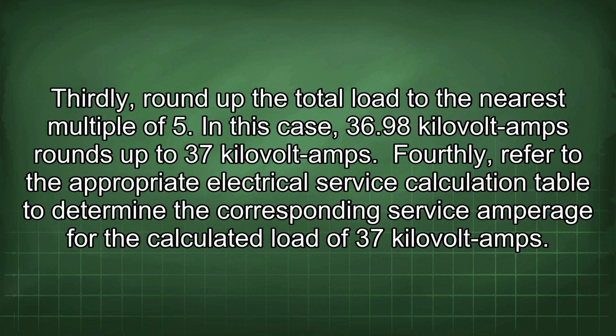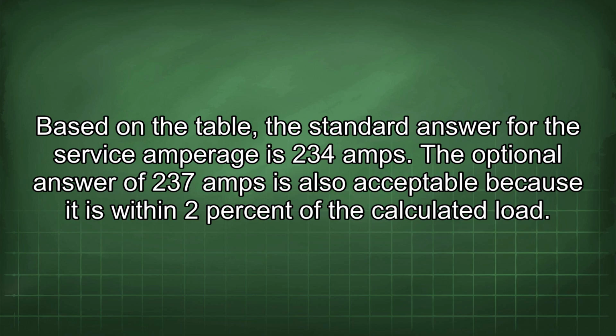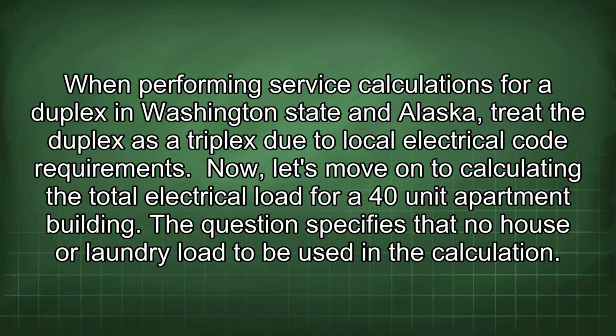Fourthly, refer to the appropriate electrical service calculation table to determine the corresponding service amperage for the calculated load of 37 kVA. Based on the table, the standard answer for the service amperage is 234 amps. The optional answer of 237 amps is also acceptable because it is within 2% of the calculated load. When performing service calculations for a duplex in Washington State and Alaska, treat the duplex as a triplex due to local electrical code requirements. Now, let's move on to calculating the total electrical load for a 40-unit apartment building.